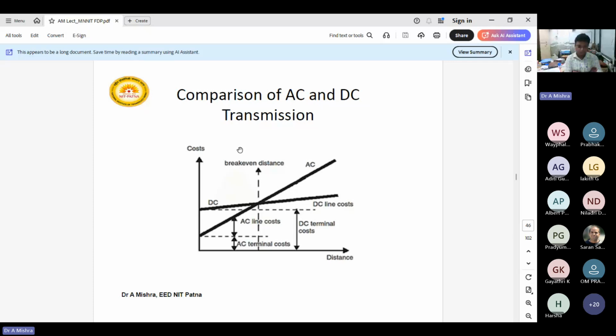The cost of the transmission will be low, but one thing you can say is that your existing system is an AC system, so changing the infrastructure will cost something more. But at the end, once you install the line, you will find your running cost is also reduced in DC transmission because your compensation requirement and your conductors are less. So all that infrastructure cost as well as the running cost will be reduced if your distance is more than 500 kilometers.